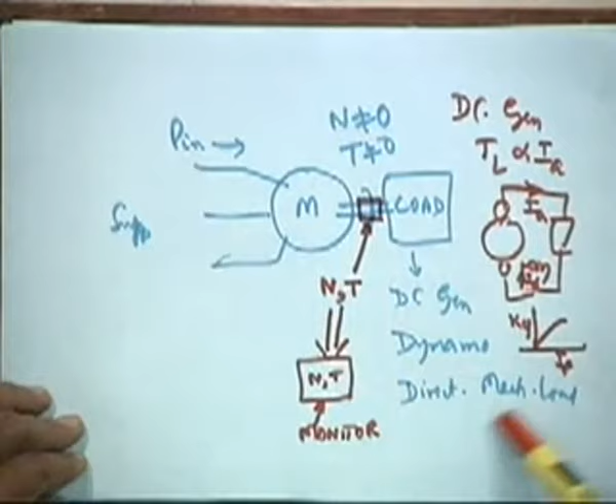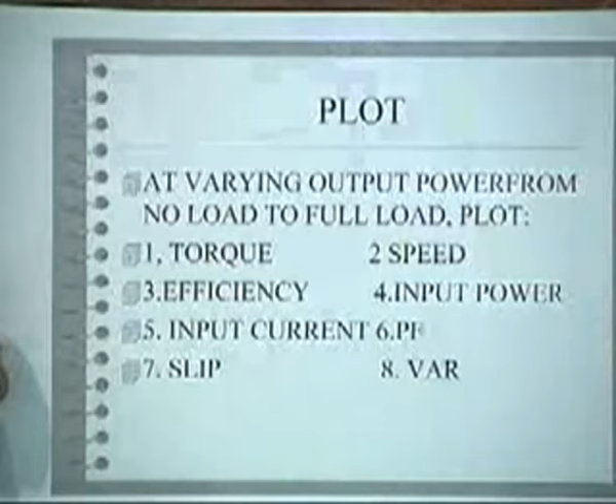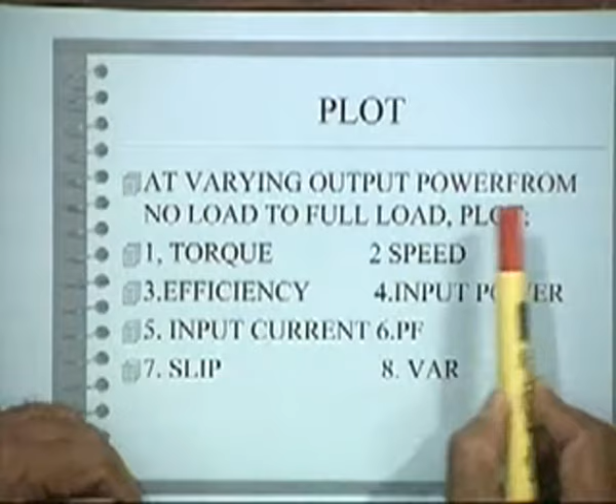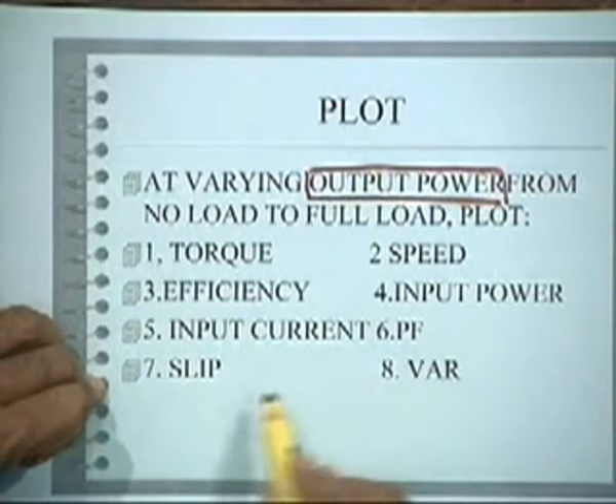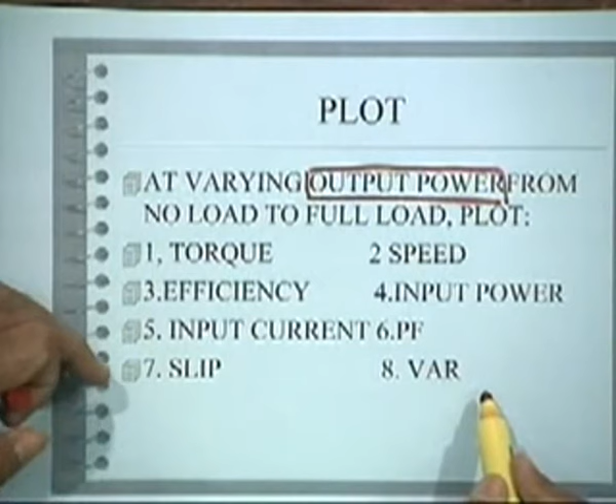Now let us assume that you have done this test and taken the input and output readings. You can do various calculations, and you plot them at varying output, because the output is varying as you load it. You vary the output power from no load to full load. At no load it is nearly synchronous speed, and at full load it will be somewhat less. You plot torque versus output power, speed, efficiency, input power, input current, power factor, slip and reactive power. These are the quantities you are interested to know as you vary the load.